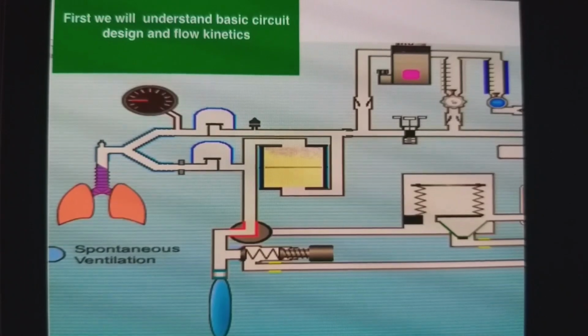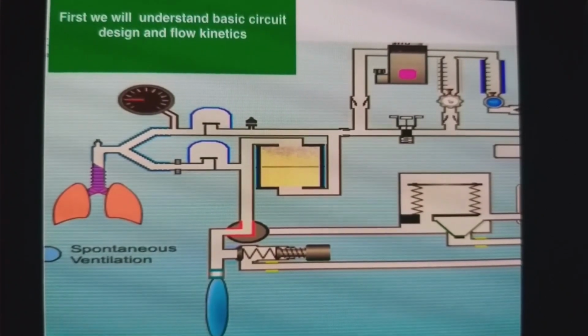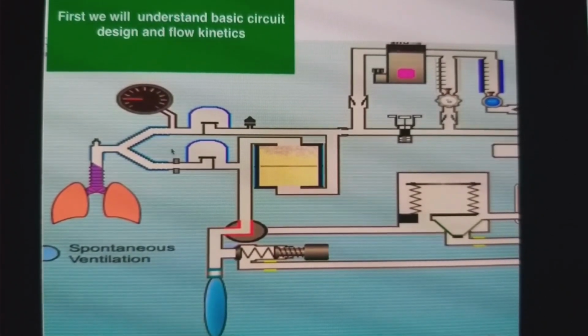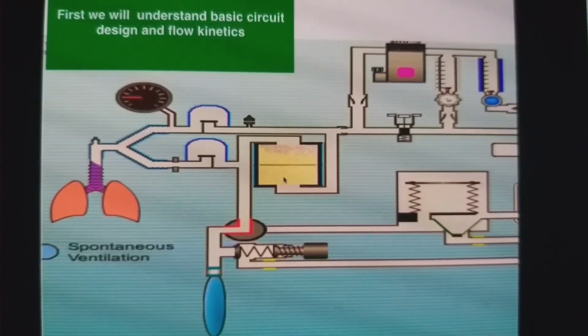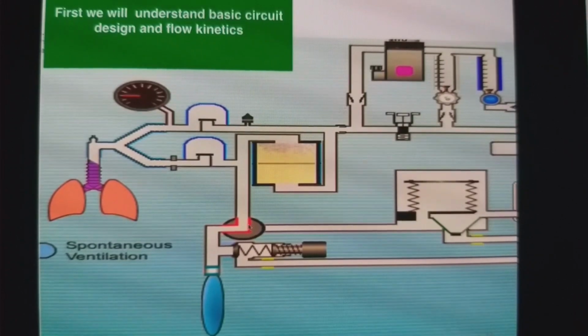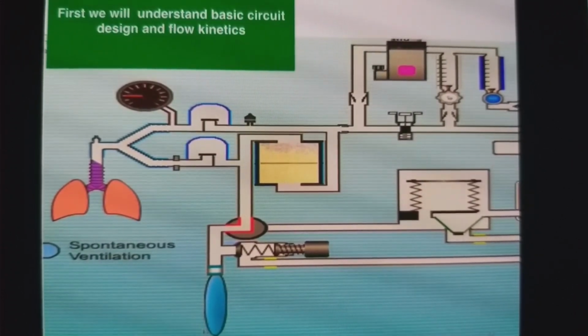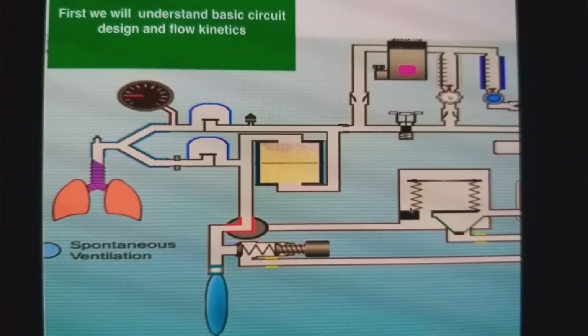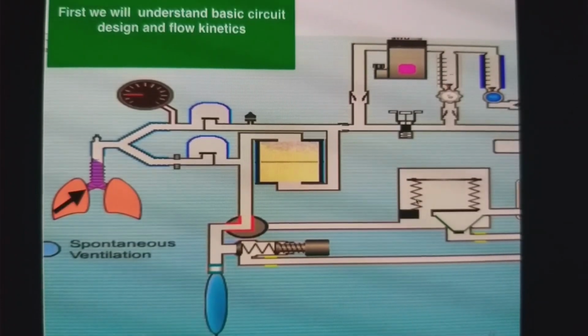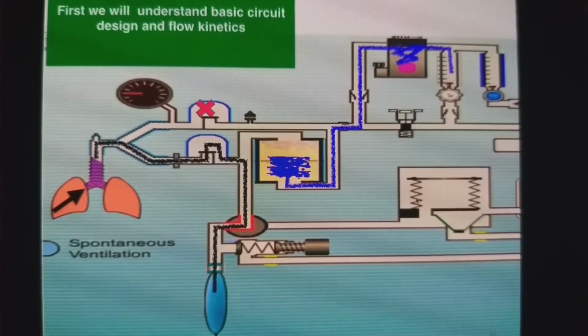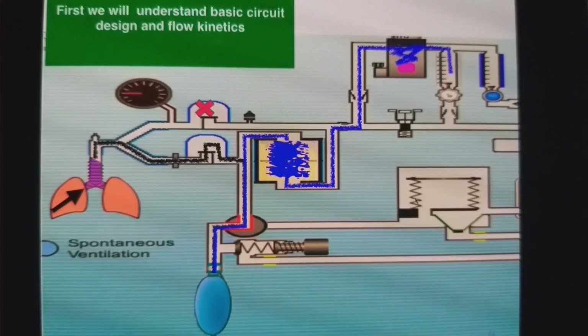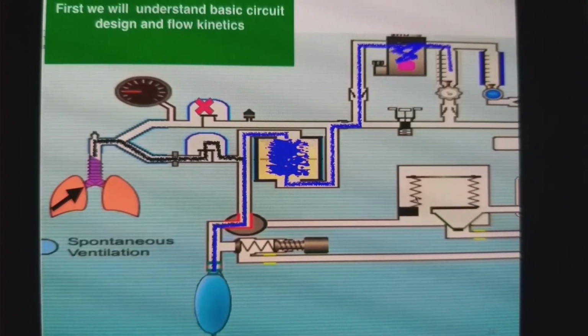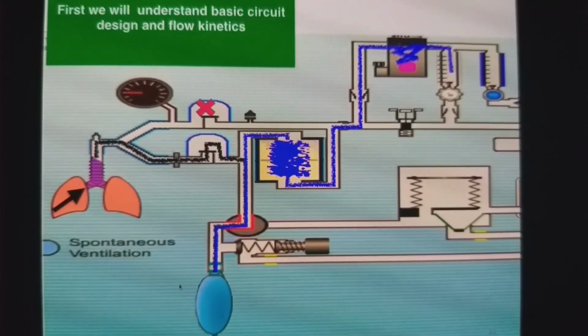This is a very simple circuit diagram, which is probably known to everyone. You know what the components are. These are the unidirectional valves, expiratory and inspiratory, and the soda lime absorber. This is the changeover switch. This is the reservoir bag. This is the APL valve, and this is the ventilator. Now, when the patient expires, the flow passes through the expiratory unidirectional valve and goes to the reservoir.